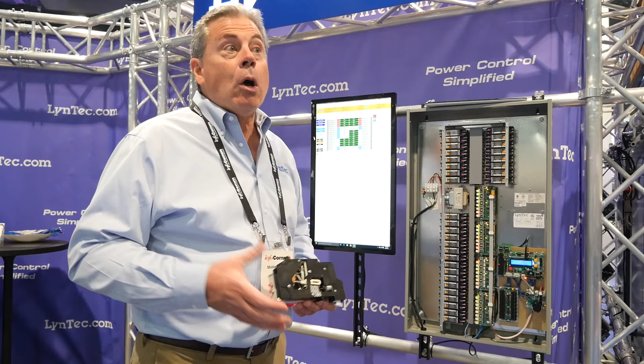There's a trend toward more LED lighting and moving to 208 volt power as opposed to 110. In a motorized circuit breaker, you could go up to a 3-pole 30 amp - anywhere from a single pole 15 all the way up to a 3-pole 30 - and still turn that load on and off as needed. With relays, we can go up to 20 amp, 30 amp, 2-pole 20, and up to 480 volt if you need to control parking lot lights, for instance.